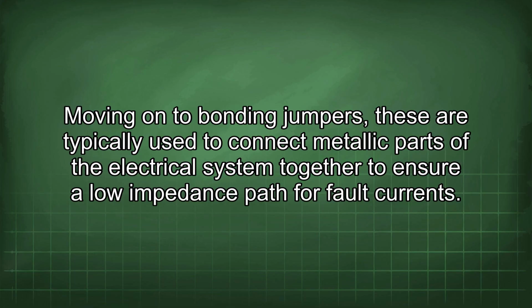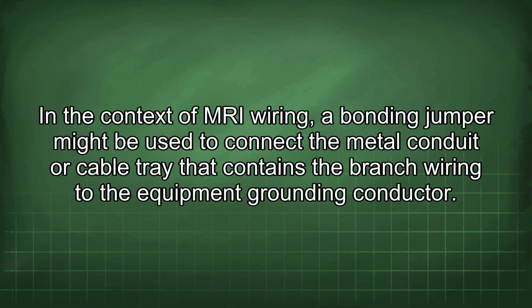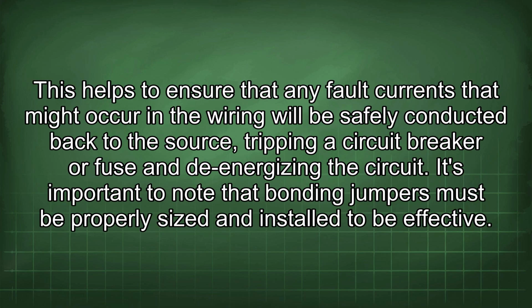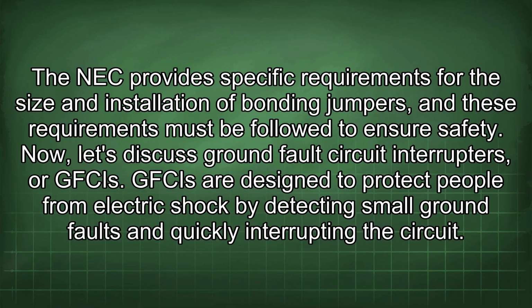Moving on to bonding jumpers, these are typically used to connect metallic parts of the electrical system together to ensure a low impedance path for fault currents. In the context of MRI wiring, a bonding jumper might be used to connect the metal conduit or cable tray that contains the branch wiring to the equipment grounding conductor. This helps to ensure that any fault currents that might occur in the wiring will be safely conducted back to the source, tripping a circuit breaker or fuse and de-energizing the circuit. It's important to note that bonding jumpers must be properly sized and installed to be effective. The NEC provides specific requirements for the size and installation of bonding jumpers, and these requirements must be followed to ensure safety.